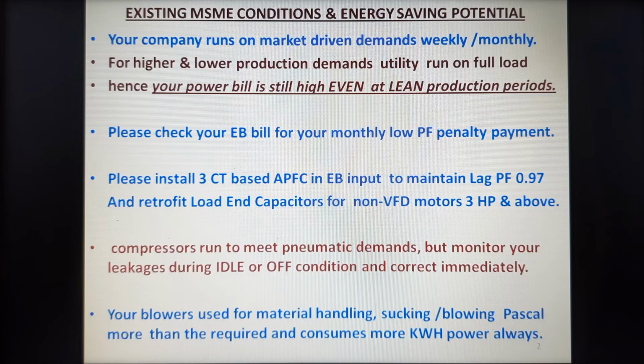Let us also see to it that the 3CT based APFC is working at the EB incoming side, so as to maintain a just slightly lagging power factor of around 0.97. Let us try to retrofit the load end capacitors on all the non-VFD motors of 3 HP and above, so that our power factor is always around 0.97 at the EB incoming side.